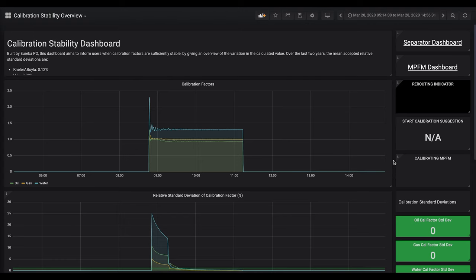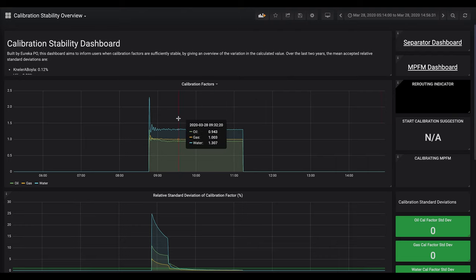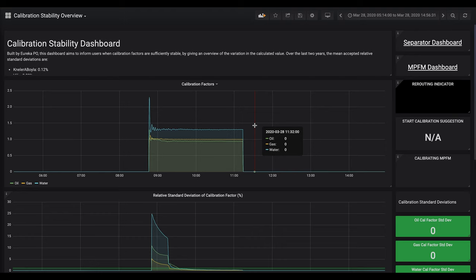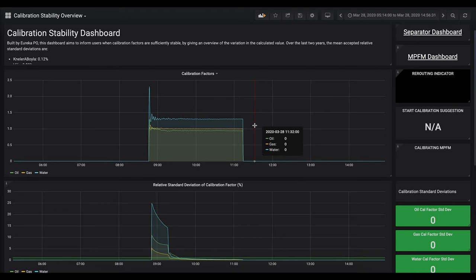This is the main dashboard that the operator will use when they're using our solution. At the top you can see the calibration factors for oil, gas, and water. These are found by integrating what's measured out of the separator versus what's measured by the multi-phase flow meters. These are what we want to be stable so that they can end the calibration.